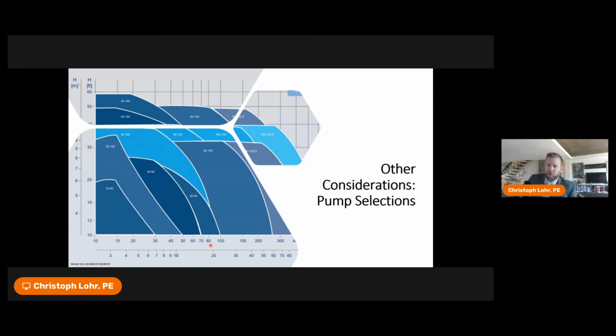So one of the trends I think that was also worthwhile seeing is that you're going to see many hot water return pumps switch from a constant speed type to a variable frequency drive, or ECM, electronically controlled motor. Now, I think there's a lot of debate among plumbing engineers right now whether a VFD pump should be utilized in conjunction with the automatic balancing valves. In part, if you're sizing your system correctly, the pump should be running all the time. But I think there's an argument to overcome in terms of if the system is going between closed state and open state, that the pump can respond accordingly.